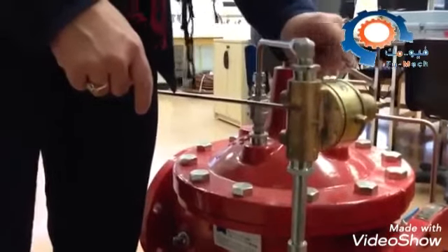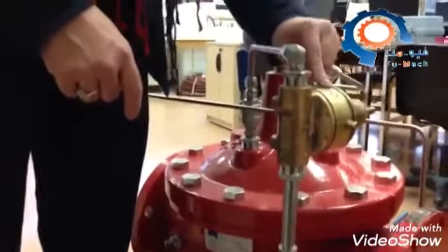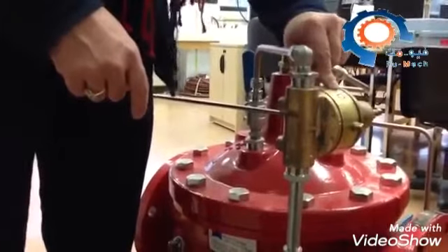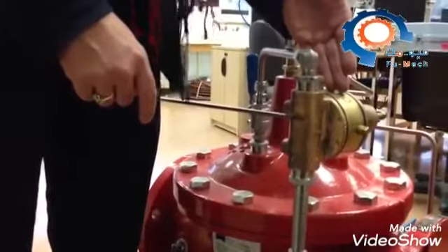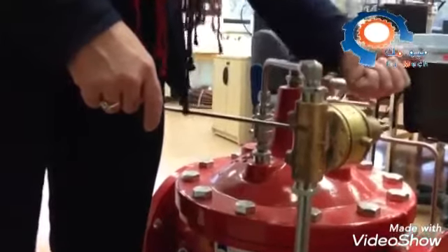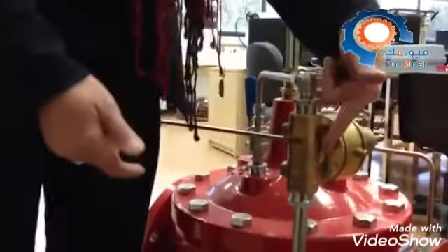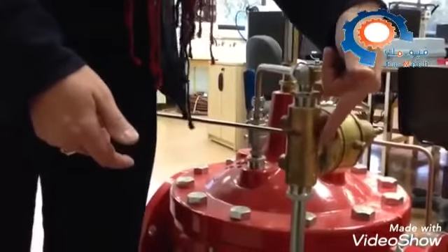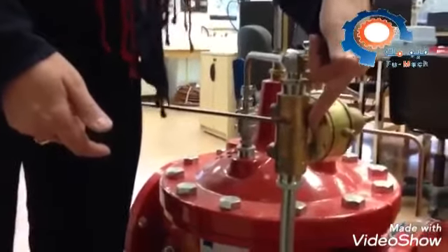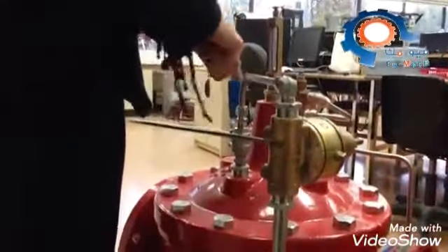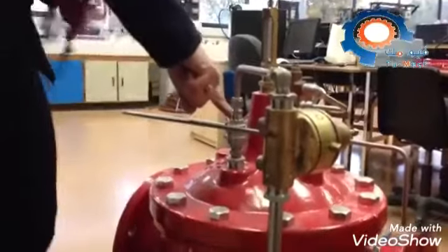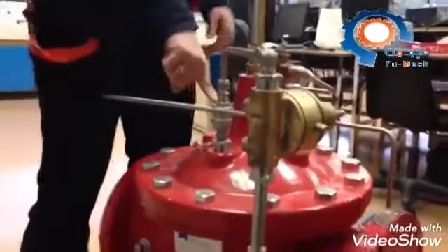If the pressure rises in this little chamber here, this one is going to start to fill up with pressure in here that overcomes the spring force, will force the stem to travel in this direction, lifting the disc off the seat in the main valve, and putting water onto this diaphragm. And then that will allow this to open, and it puts water on top. Now here's the ticket.